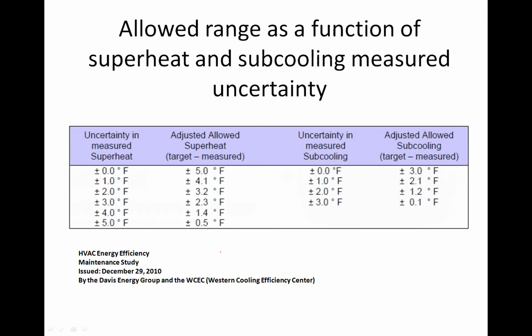Now, I told you we weren't off the hook yet, so let's talk about the allowable range as a function of superheat and subcooling. Again, if we had a gauge with no uncertainty in our subcooling measurement, in other words, if the gauge said 10 degrees of subcooling, it was exactly 10 degrees of subcooling. Now, even with a high-end digital gauge, 0.5% accuracy, we said we're plus or minus 2.8. If you're talking 2.8, you're talking right here between 2 and 3. We have to be within 1.2 to 1/10 of a degree of our subcooling. Basically, when we look at it this way, we have to be within 1 degree.